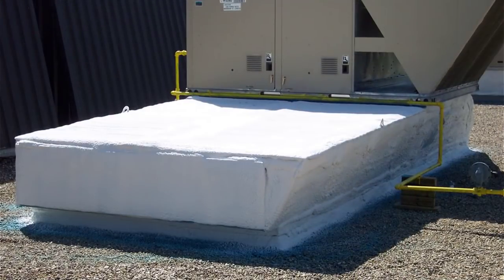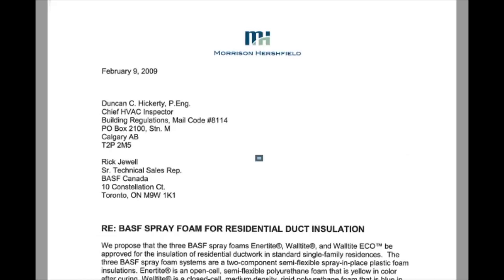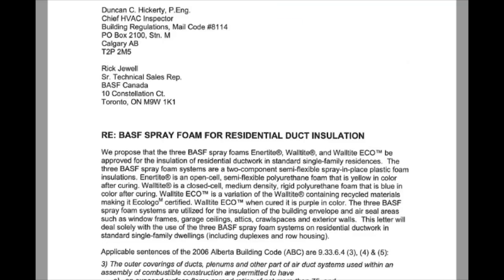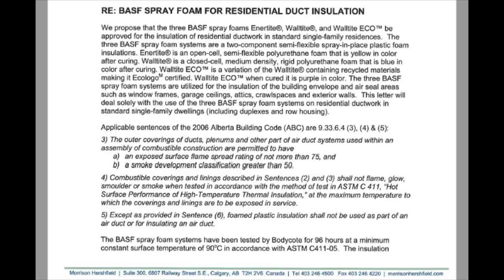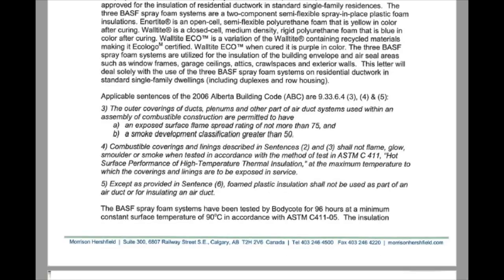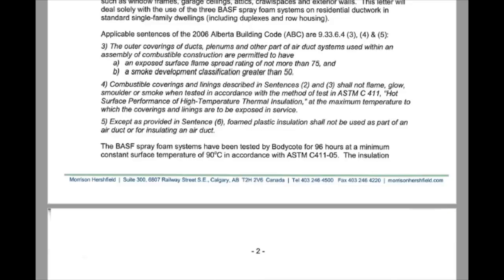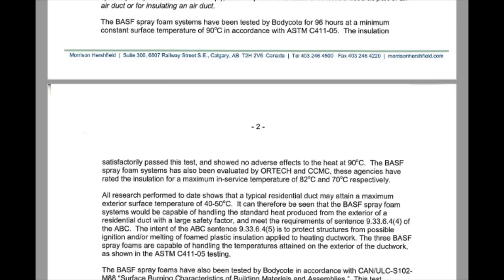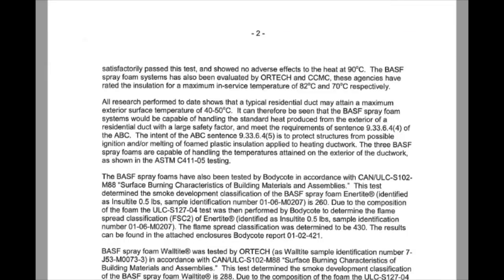So it's a good way to go, but you have got to have your approvals in place. Do not start spraying the ductwork without having your suppliers' paperwork in order and having the authorities having jurisdiction in your area approve it. If you do not, they will not approve it, and they'll make you dig it out, and you'll be looking at thousands upon thousands of dollars of replacing that ductwork and cleaning all the foam off, and you'll look like a horse's rear.